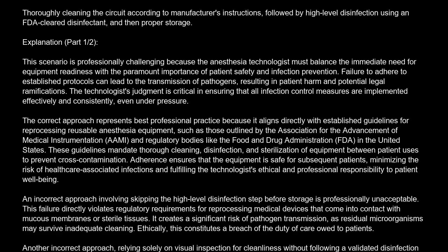The correct approach represents best professional practice because it aligns directly with established guidelines for reprocessing reusable anesthesia equipment, such as those outlined by the Association for the Advancement of Medical Instrumentation (AAMI) and regulatory bodies like the Food and Drug Administration (FDA) in the United States. These guidelines mandate thorough cleaning, disinfection, and sterilization of equipment between patient uses to prevent cross-contamination.